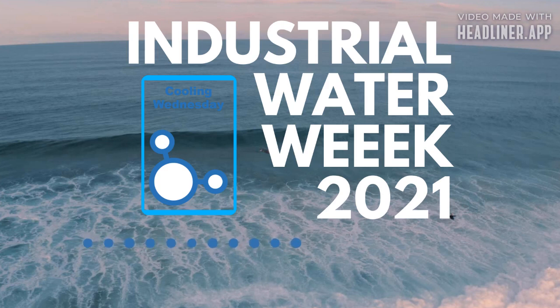A lot of municipalities are giving credits for the amount of water that's being evaporated, which is about 90% of all the water that comes into the cooling tower, versus going down the drain. Now, here in Atlanta, we have very old infrastructure, and it costs more to get rid of the water that you bought than it did to buy it. So it really makes sense to take advantage of that credit. So we have water meters on the incoming water on the makeup, and we have meters on the bleed. Our customers then record those numbers, and they're able to get a credit.